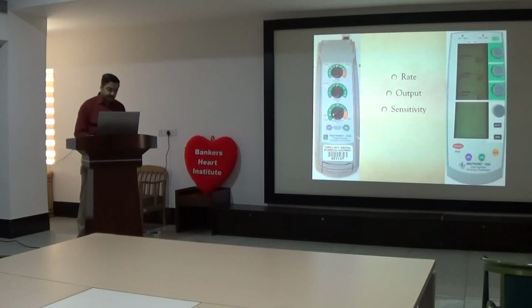So rate is obviously heart rate. Generally heart rate requirement is between 60 to 80. Depending on your patient's requirement, it can be increased or it can be decreased. Then output. Output is the amount of current which is delivered to the lead and which is ultimately delivered to the patient's ventricle. Now there is one terminology called threshold. What is threshold? Threshold is the minimum amount of output, or minimum amount of electricity, required to pace the patient's heart.